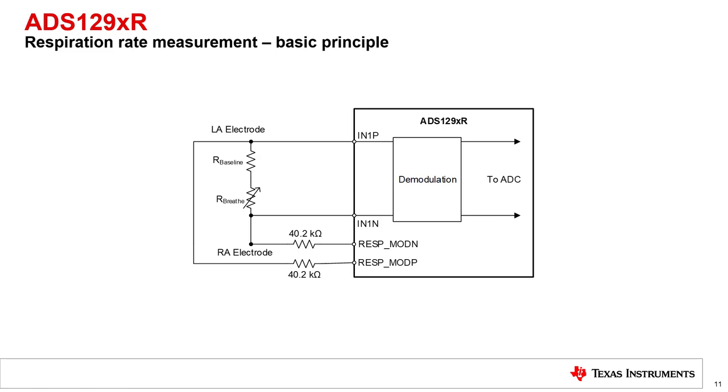As some applications also require the measurement of a patient's respiration rate, the R version of the ADS129X includes an integrated respiration feature. This feature measures the patient's respiration through a technique known as impedance pneumography. Essentially, this technique aims to measure the small changes in impedance across the thoracic cavity or chest as the patient inhales and exhales.